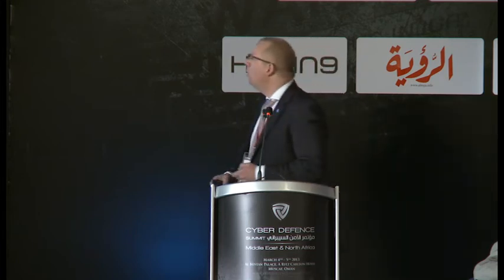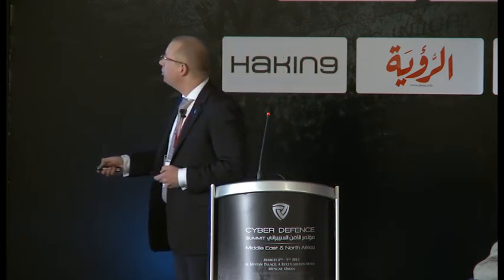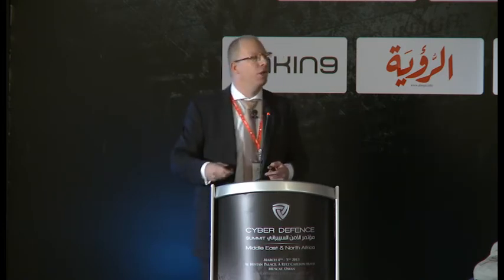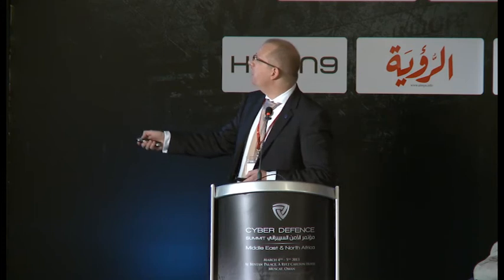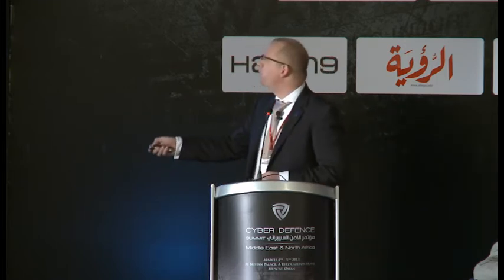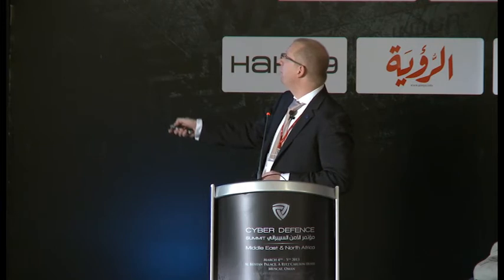And control systems in the past were looking like this. You got the control system here, temperature, actuator, something which is called a programmable logic controller, a small intelligent device, and the SCADA system on top of this running some proprietary operating system from Digital, for example, or VxWorks or something else. This is hooked up on a network. It's called a bus, a field bus here, Profibus, Modbus, connecting to other sensors, other actuators, more PLCs, some operator terminal, and even some more controllers. And there's a hierarchy, so you can build up now a network of networks.